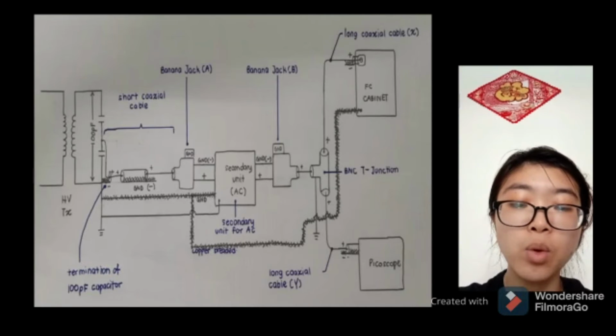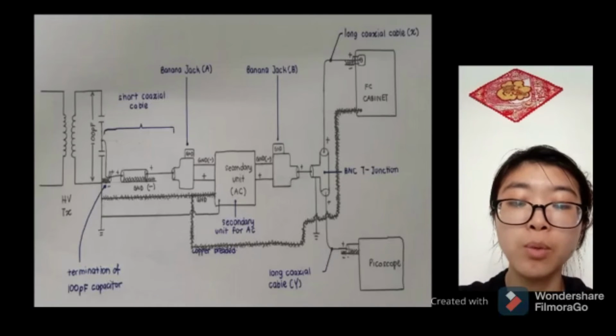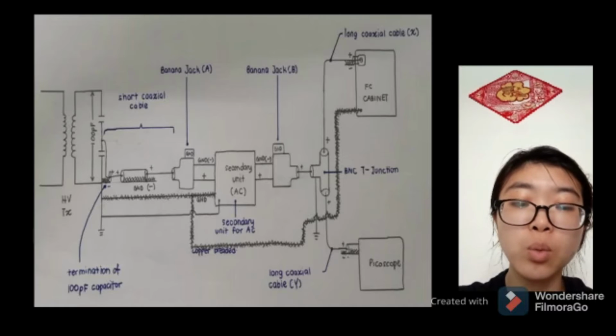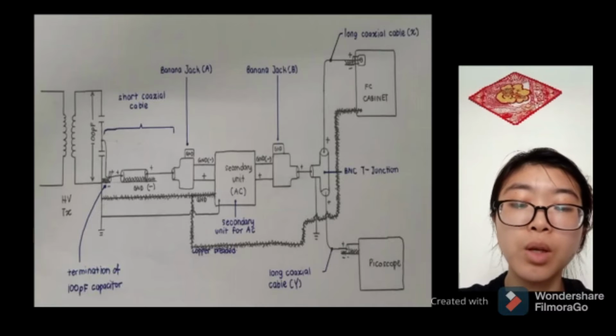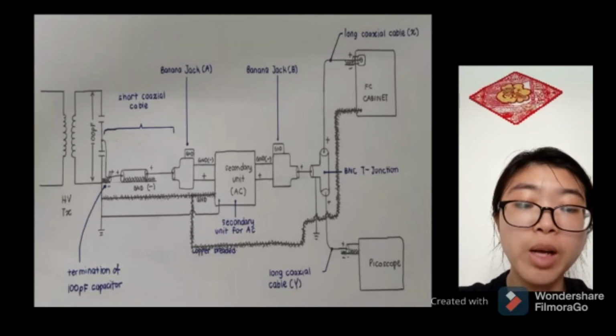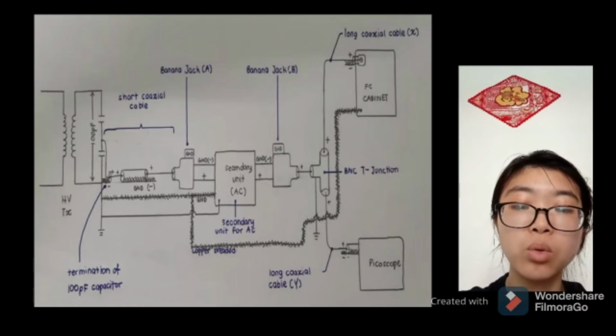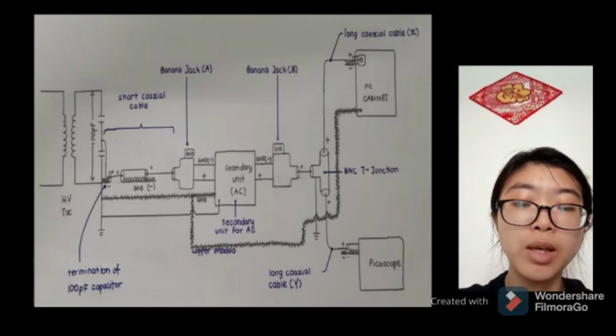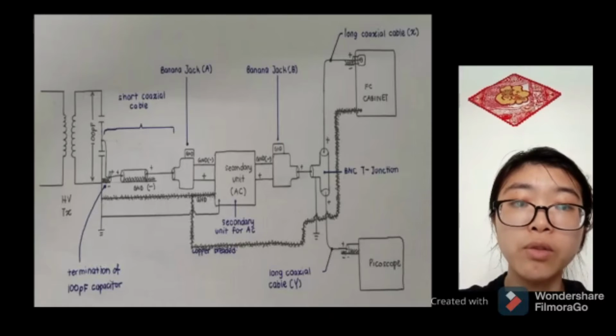Ensure that every time we get inside the testing plant, we must use special gloves, which are rubber gloves, before touching. Reduce the voltage of the generator for safety when touching around the high tension and high stress area. For double safety, we can discharge by using the grounding rod to touch the surrounding of the measuring capacitor. Remember to hold the end of the grounding rod.